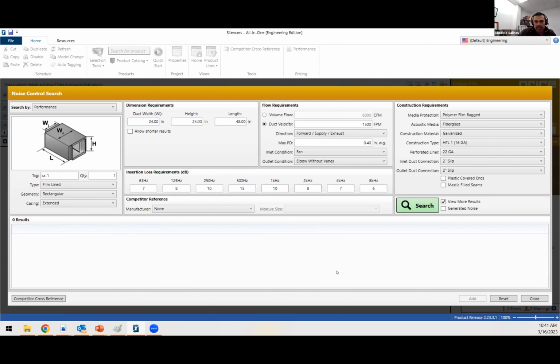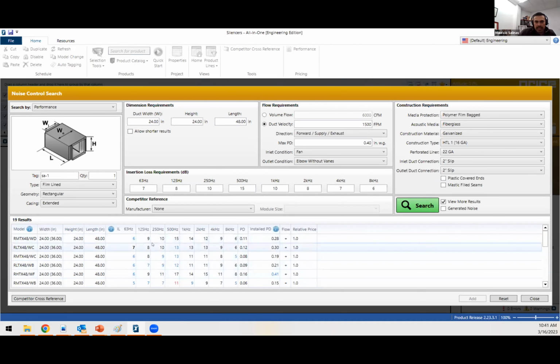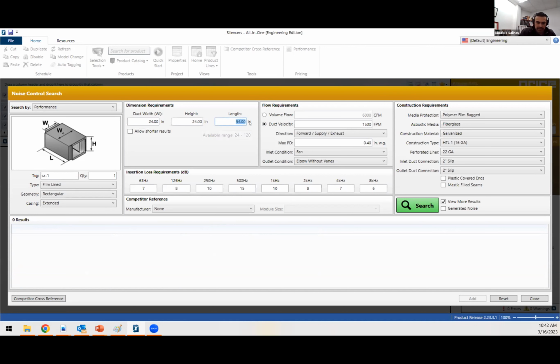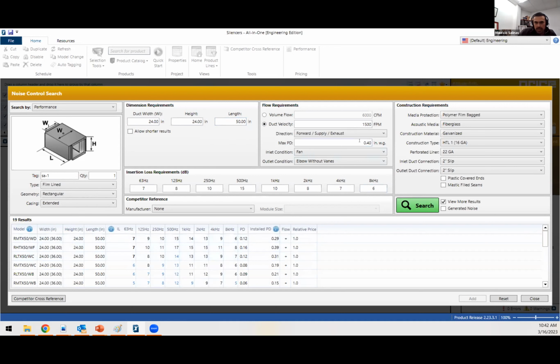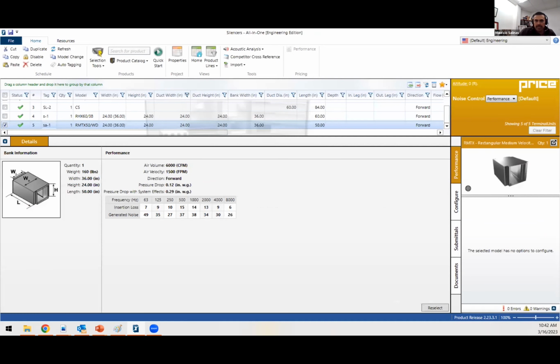The longer the silencer, the better it's going to perform. And now you can start seeing that all your numbers are starting to become dark. Right, so in this specific case, if we add another few inches, you'll see that we get close to performance now. And you're going to meet it under 1/3 of an inch installed that we were looking for. So that is one way to select silencers. And then when you close that window, you're just going to have your dimensions, your weight, your CFM, feet per minute, pressure drop installed, insertion loss, and also very importantly, generated noise.